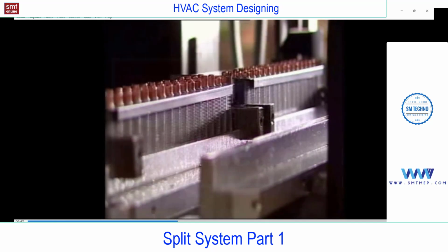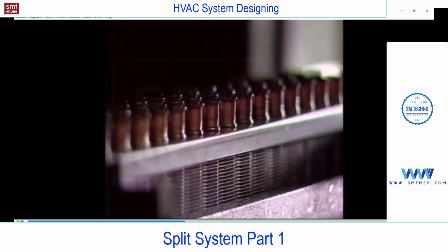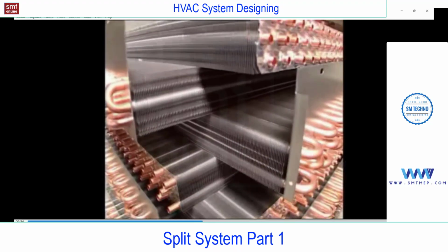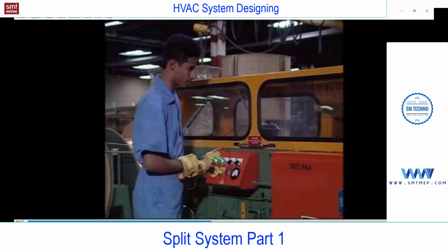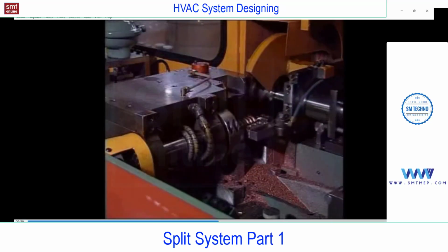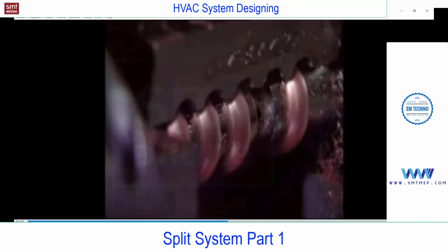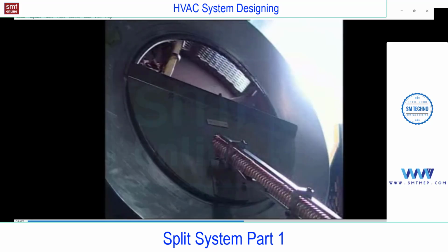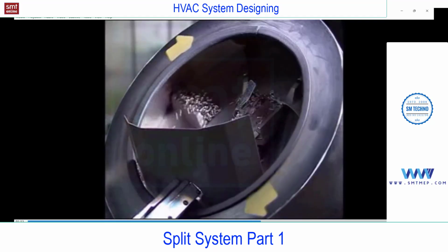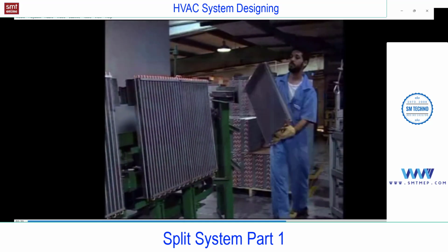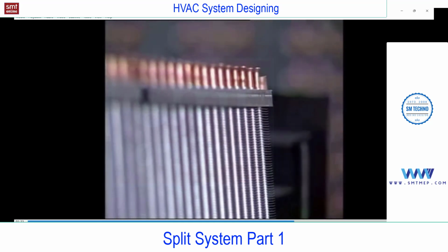Exchanger coils. Coils are then moved to the mechanical tube expander, where mandrels are inserted to each tube, which mechanically bond the hairpin tube to the aluminium fins. The return bend machine fabricates copper return bends or elbows from copper reels, and then the brazing rings are inserted mechanically. One final step completes the circuiting loop for the successful flowing of refrigerant through the heat exchanger coils.